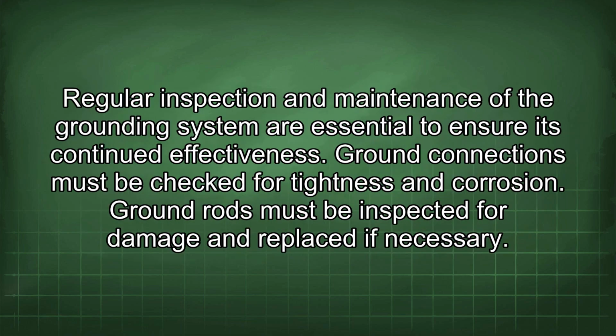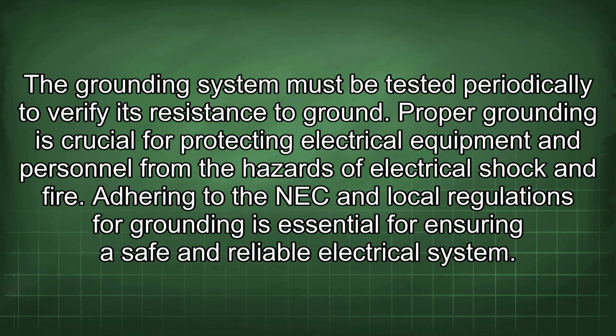Regular inspection and maintenance of the grounding system are essential to ensure its continued effectiveness. Ground connections must be checked for tightness and corrosion. Ground rods must be inspected for damage and replaced if necessary. The grounding system must be tested periodically to verify its resistance to ground. Proper grounding is crucial for protecting electrical equipment and personnel from the hazards of electrical shock and fire. Adhering to the NEC and local regulations for grounding is essential for ensuring a safe and reliable electrical system.